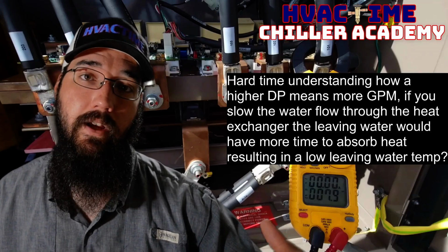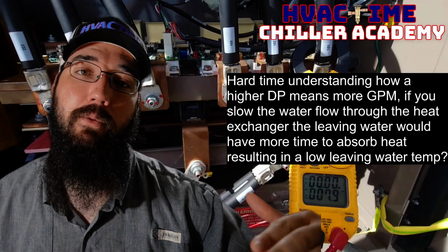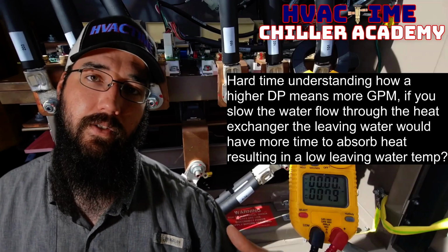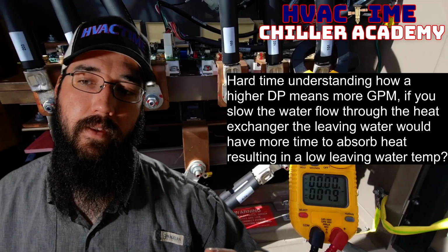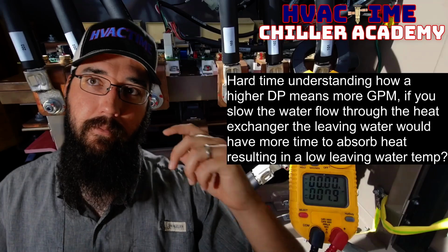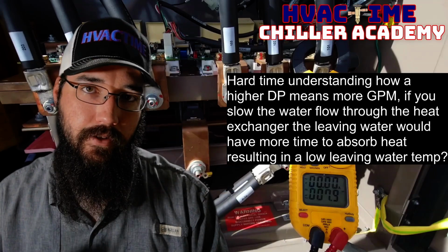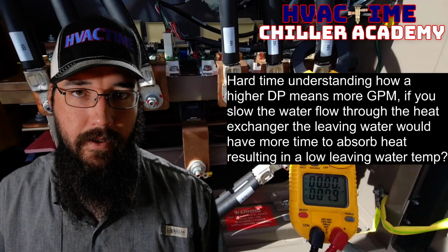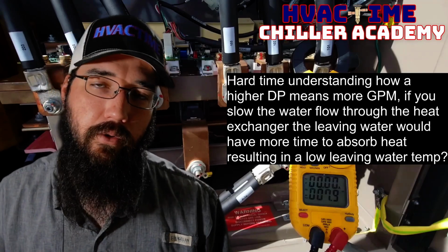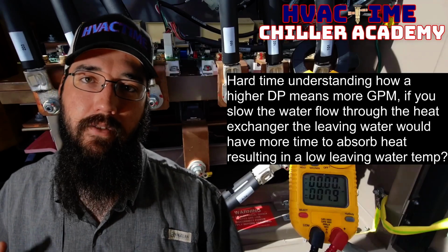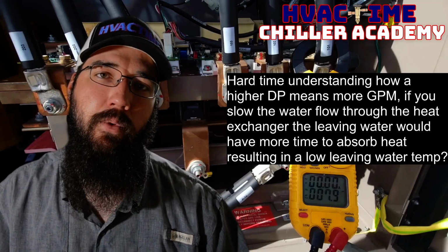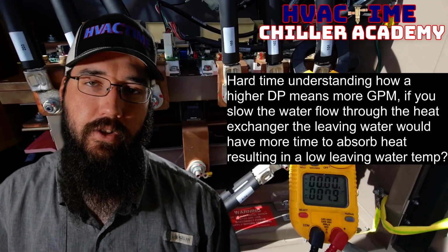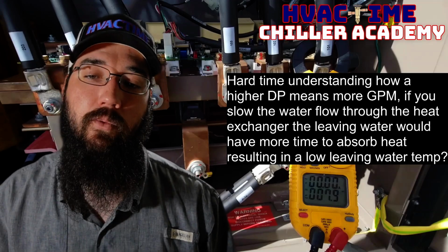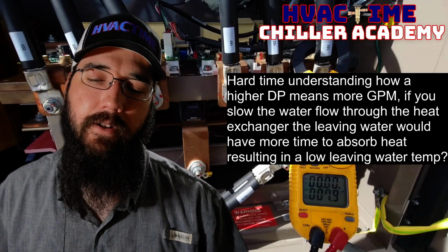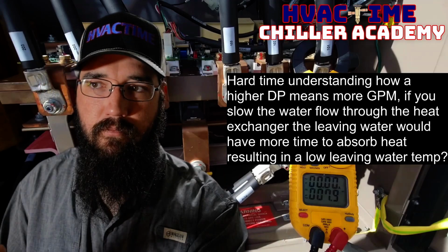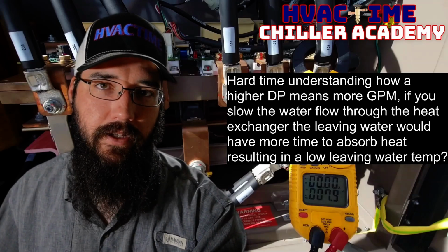Eventually, that entering water side is going to start to rise and increase, and we'll have even higher and higher temperature differences, even though we're technically at design conditions in terms of temperature difference at the chiller. And that could be a symptom of low GPM. So if we're not moving enough flow through the heat exchanger and we're not creating enough differential pressure, we'll hit set point even though we're not actually moving that much heat, just because there is so much contact time with that water.